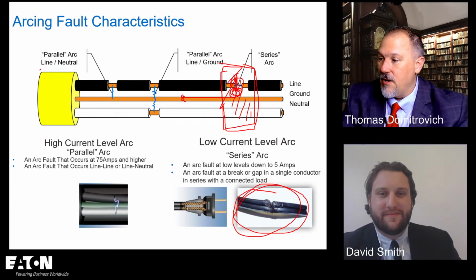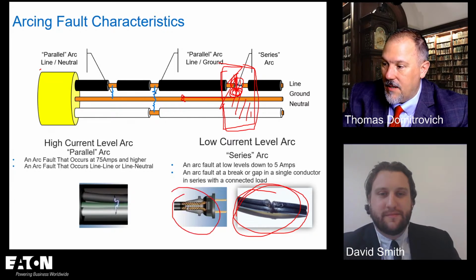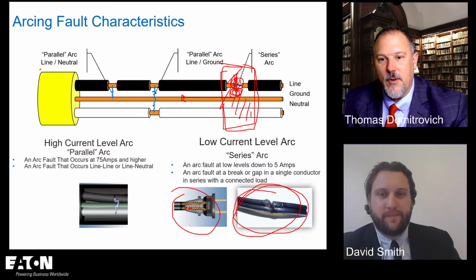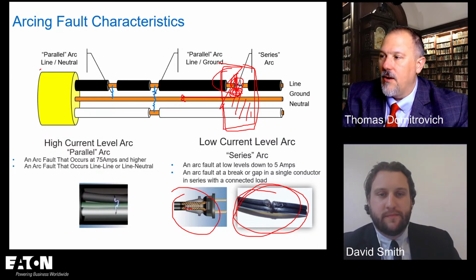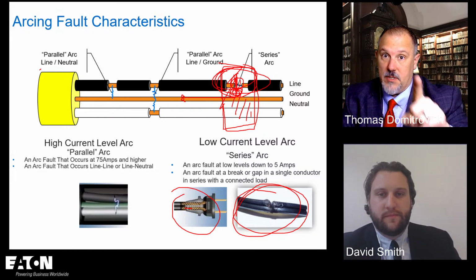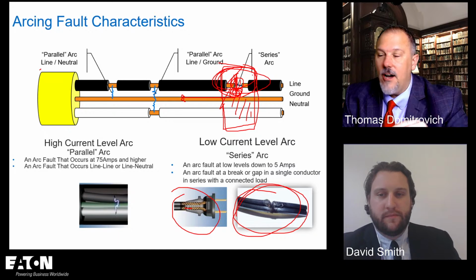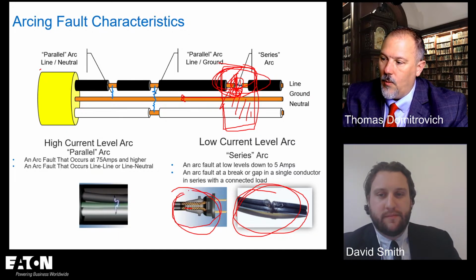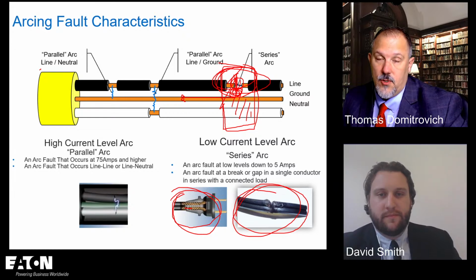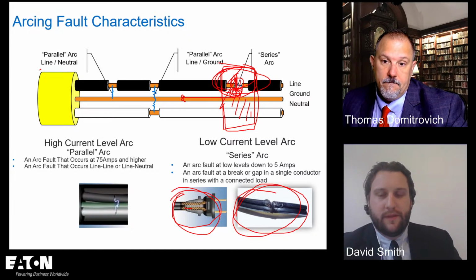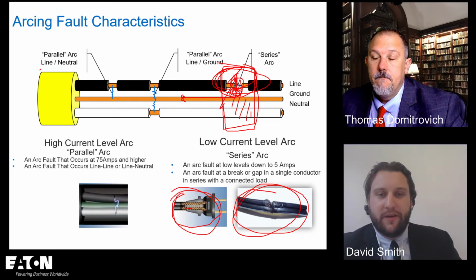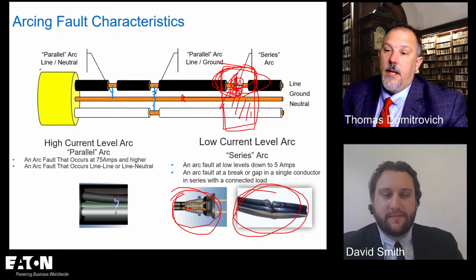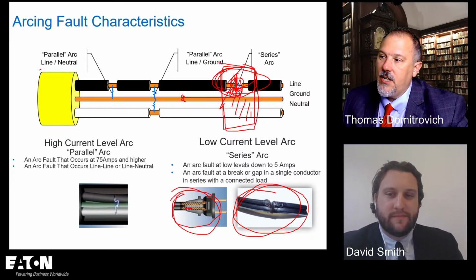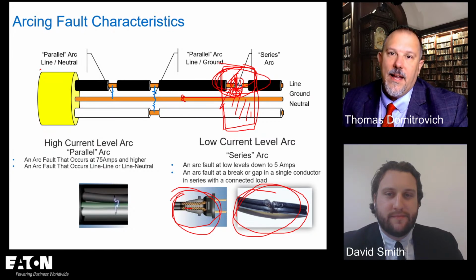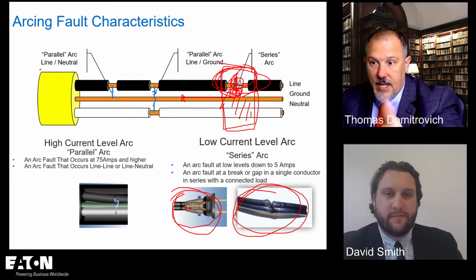But that type of an arc, and this one down here, you see what I'm breaking? Right. Yeah. I don't have an equipment grounding conductor. So up in my NM wire, I could detect this series arc at 5 amps, no doubt. But I could not detect a 5 amp arc when I don't have an equipment grounding conductor, because the method I used was GFPE. Friend of the show, Mike King, asking if there's any significance to the 5 amps. All right. I could not find why that 5 amp.